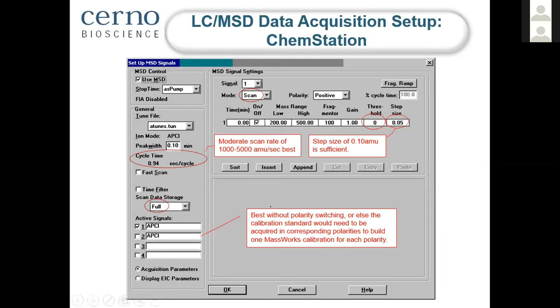In the LCMS system, there is a capacity of enabling additional channels, including polarity switching. You can switch between positive mode and negative mode and interleaving them. That's doable. It's also compatible with MassWorks, but we recommend at the beginning you stay with only a single mode, single polarity, either positive or negative to get started. And if you do like to do polarity switching later on, make sure you set up the mass spec method with the same polarity switching between the standard and the sample.